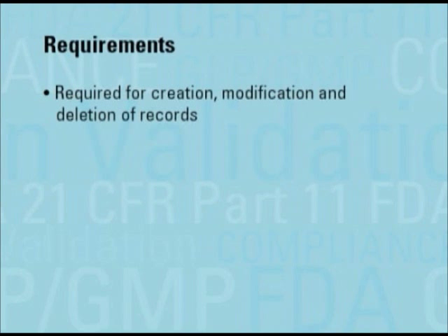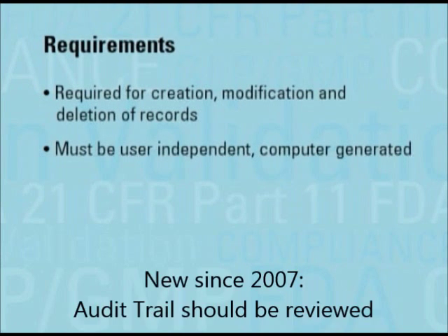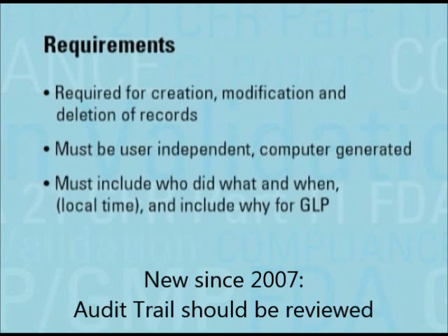They must be recorded by the computer and be independent from the operator. Audit trails should include who created, modified, or deleted a record, what was done, and when it was done.